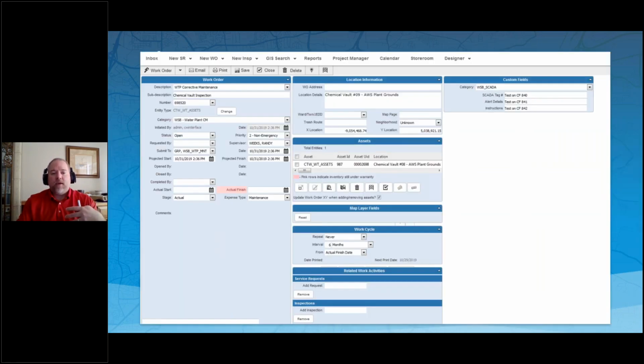So instead of making a chemical vault overflow work order, we created a water treatment plant corrective maintenance work order, which is triggered by a SCADA tag inside GE iFIX. We differentiate what it's from and for through the sub-description we send, a very specific sub-description, like 'this is a chemical vault inspection.' So we have a corrective maintenance work order that is a chemical vault inspection in the sub-description.